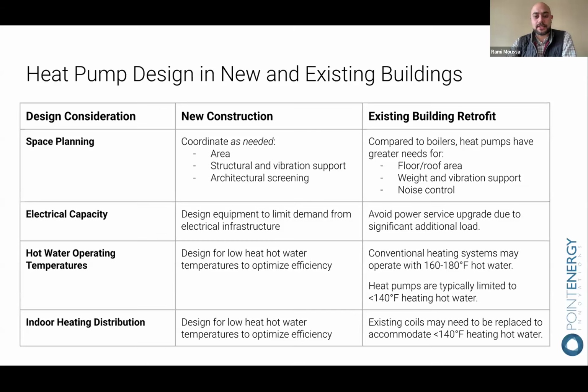Another piece I really want to hit on here is that with conventional refrigerants, there is a very specific operating range for supply hot water temperatures that we can hit. Something unique with CO₂ heat pumps is that they can actually meet more of the conventional heating system operating conditions, with hot water temperatures up in that 160, 180 degree range. So there's an opportunity here for CO₂ to cover a different range of equipment than conventional can and present some additional value.